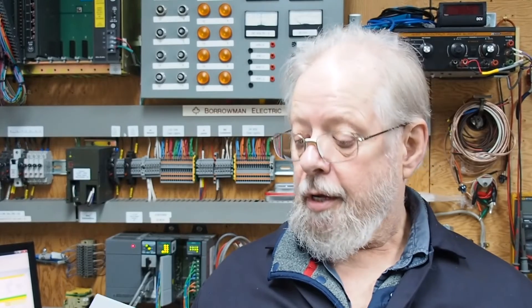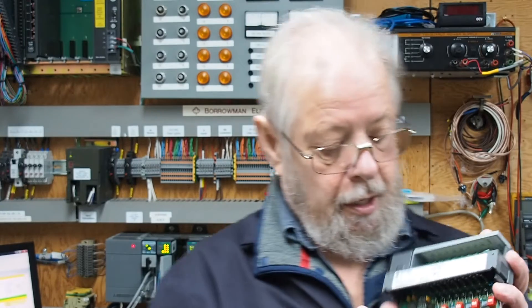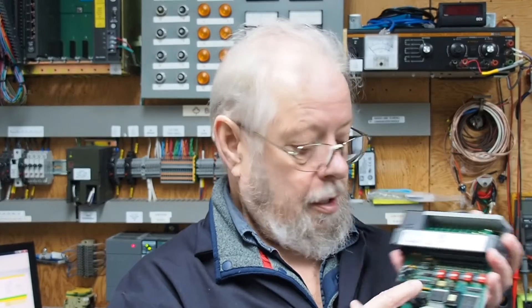The NI8, which is an 8-channel analog input, and it is either voltage or current. And the configuration for the NI8, the voltage channels and the current channels are picked by the slide switches on the card.